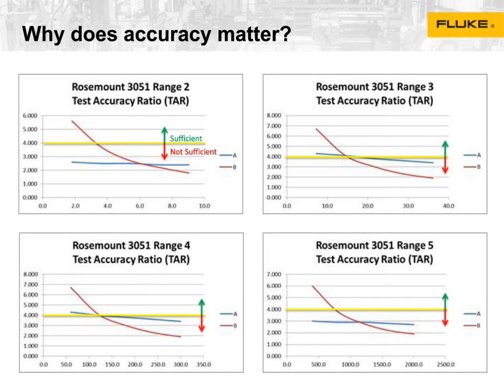And what this means is that if your calibrator is specified as percent full scale, you have more consistent performance across the range. Whereas if your calibrator is specified as percent reading, you have to be very aware of whether you're high in the range or low in the range. And if you get an out of tolerance reading, does that mean that the unit is actually out of tolerance, or does that just mean that I don't have sufficient margin in order to be doing this calibration? And so it's very, very difficult to do that.